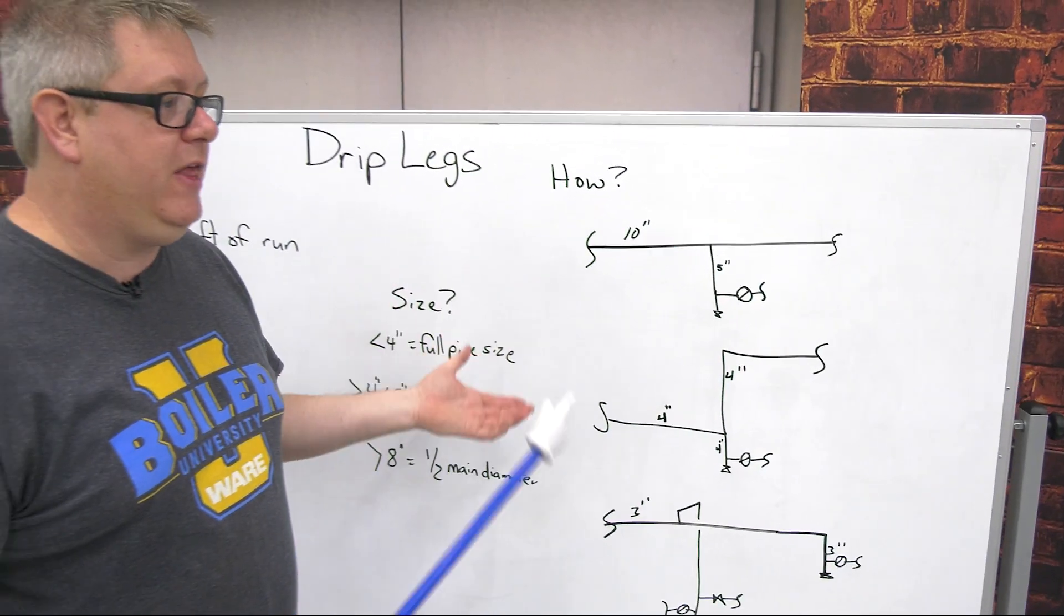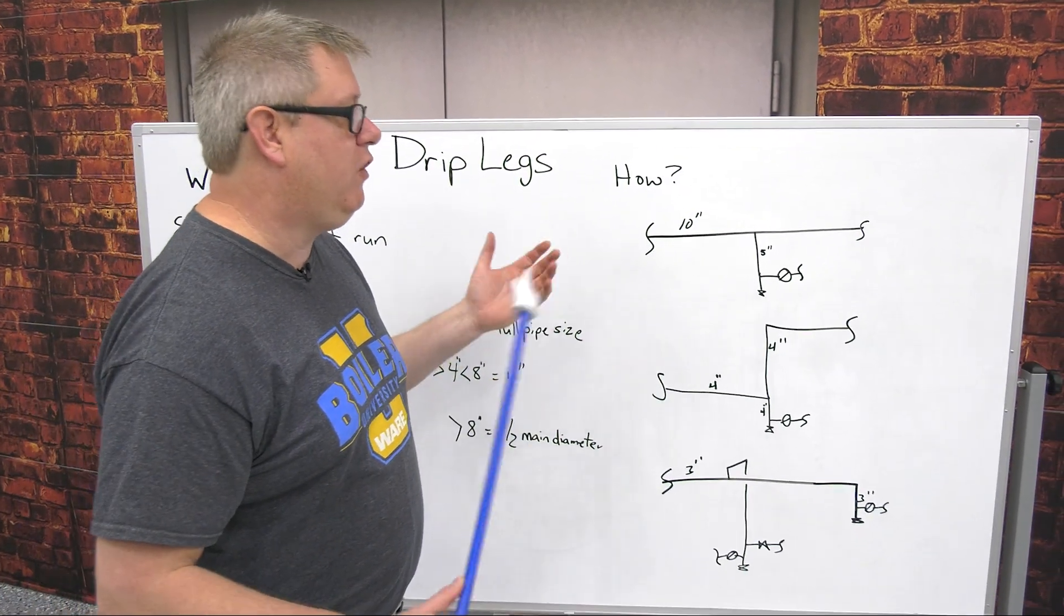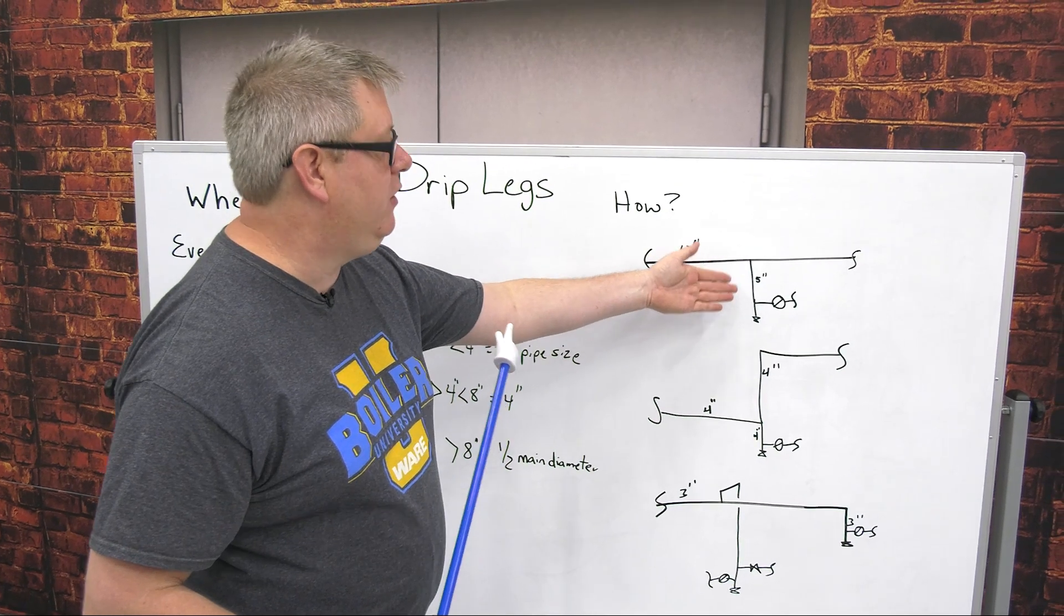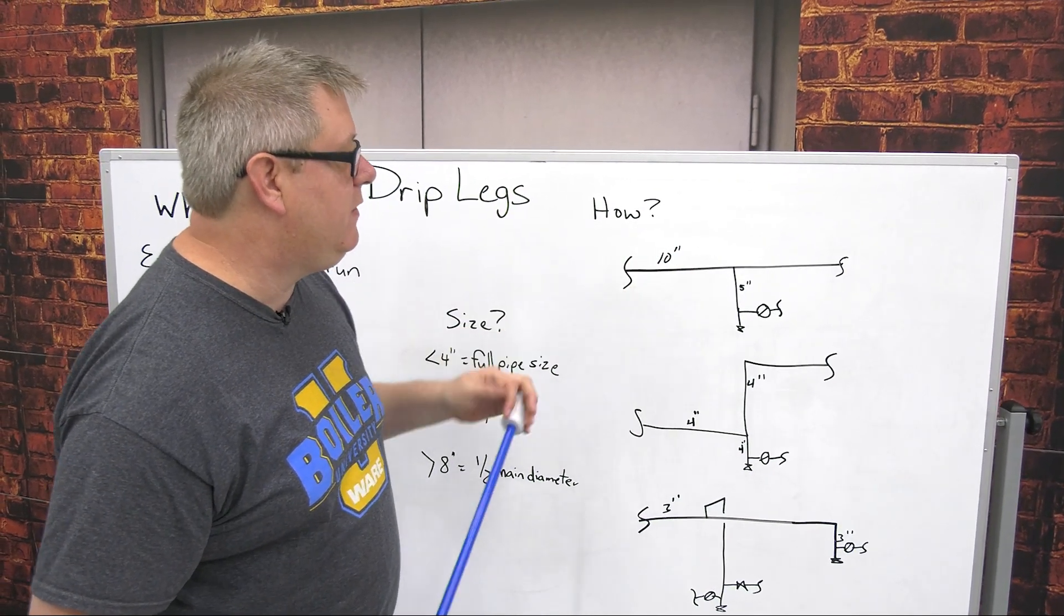In this case we would come directly off the bottom of the header, tee out the side with our trap, and we always want to put a drain on that as well for system startup. We can open that drain, clear condensate for troubleshooting, etc. There's some additional piping associated with the trap. We'll look at that next week.